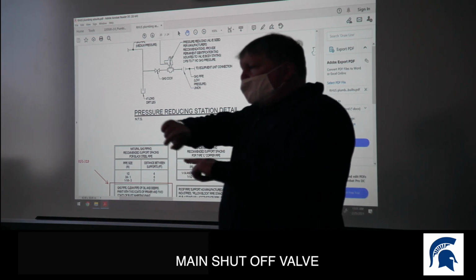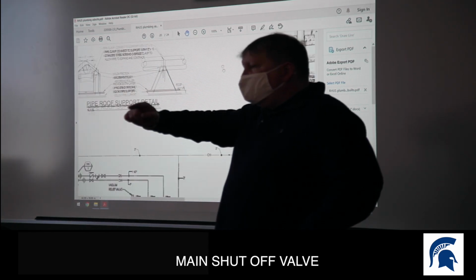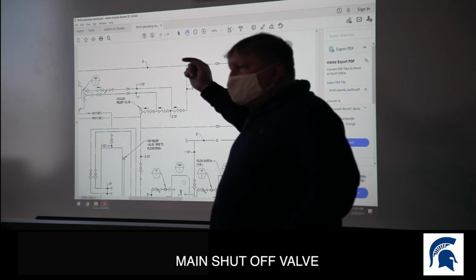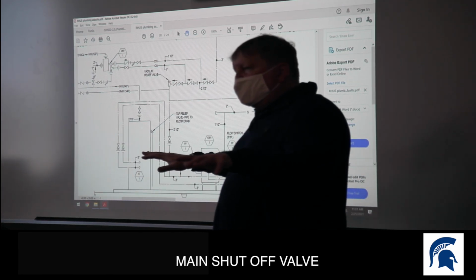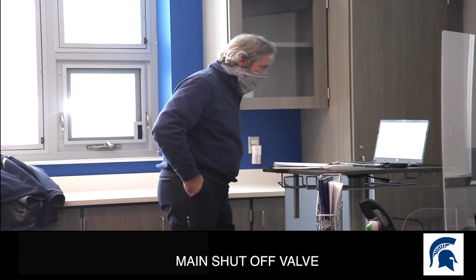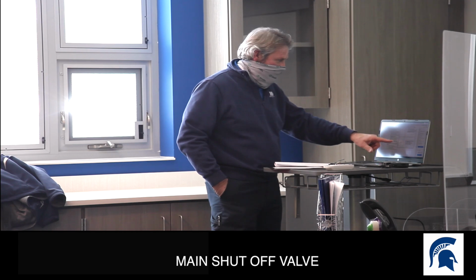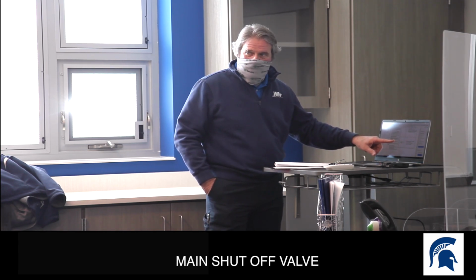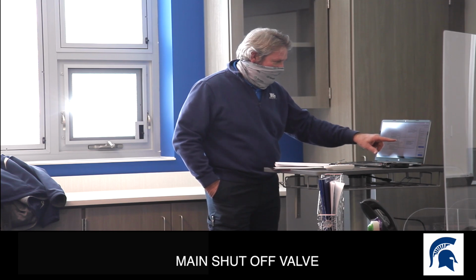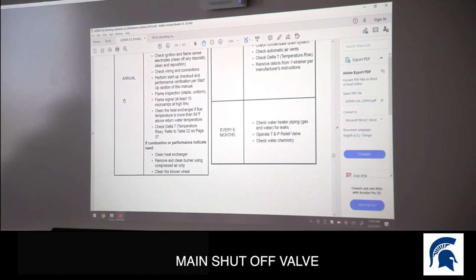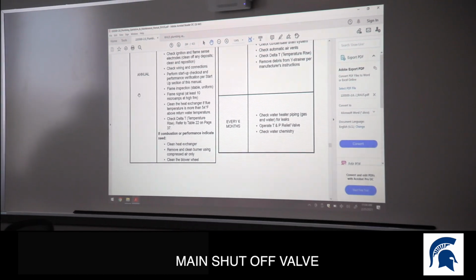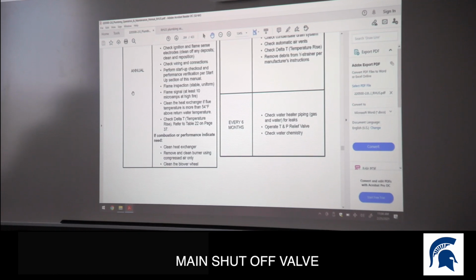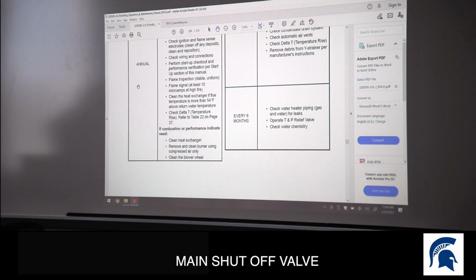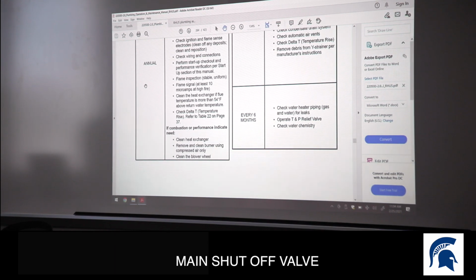So the water coming out of the water heater is 140 degrees. Okay. Water goes to the kitchen at 140 degrees. It tees off and goes to the mixing valve, mixes with cold water, and then the rest of the building is set at 115 degrees. The heat exchanger, so that goes back to the question we talked about, or what we brought up about the delta T there. So if you have a difference of 54 degrees, then you have to clean the heat exchanger, and that's where table 22 comes in. I have that. I can show that to you. Yours is on the bottom because it's the largest unit, and it gives you where you should be in that delta T. And that's the difference between your cold and your hot going out. Whatever that difference is, that's your delta T.